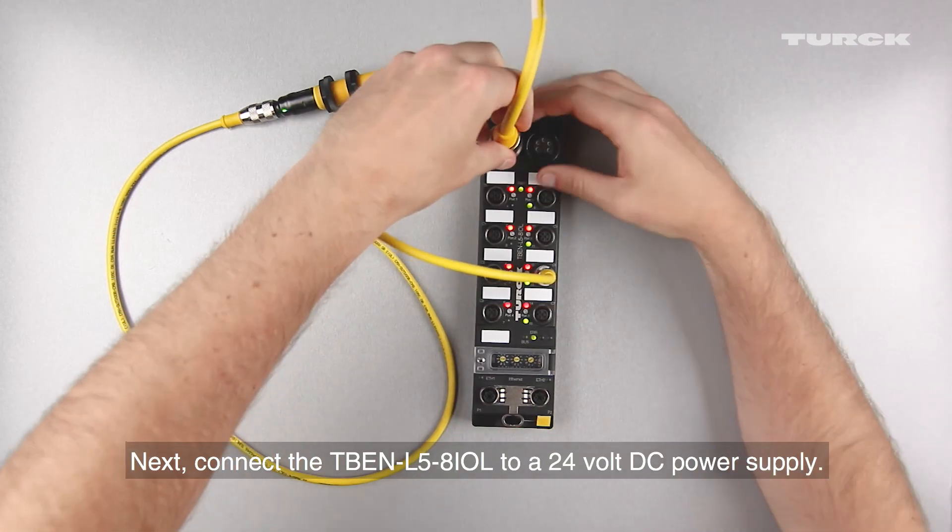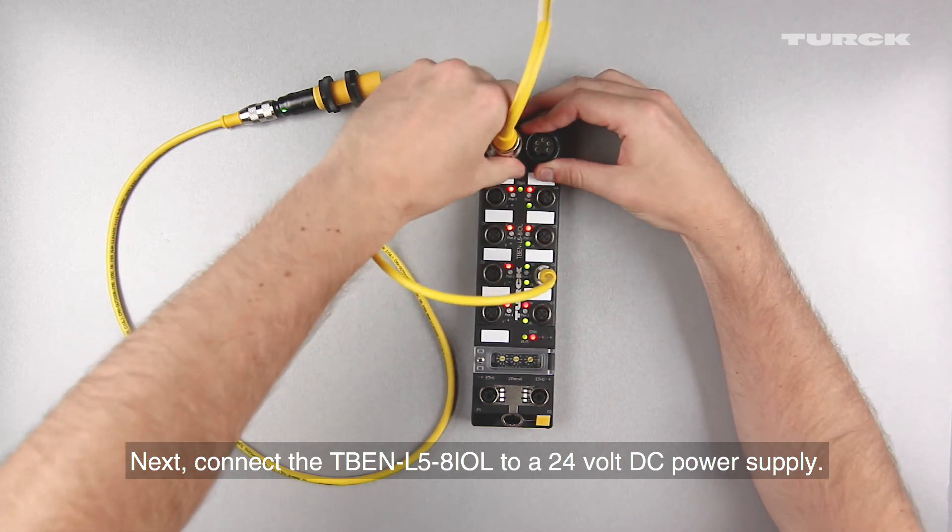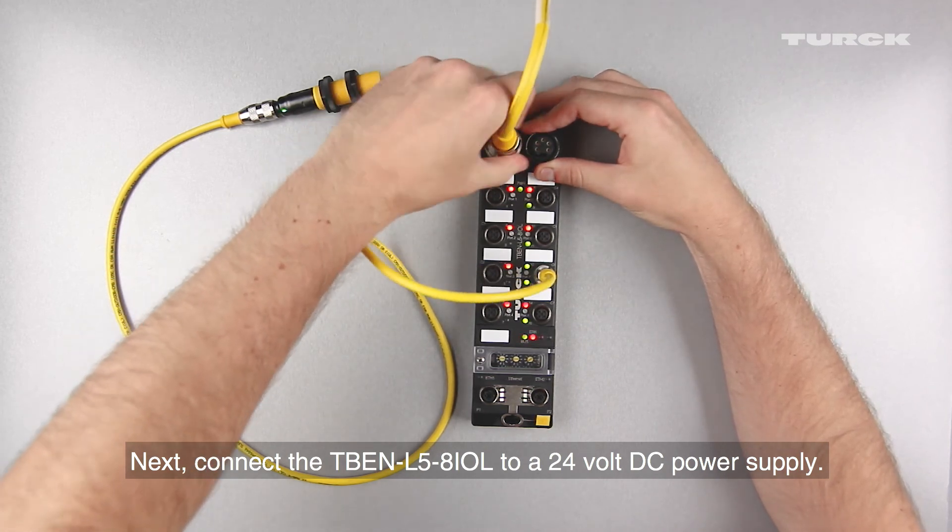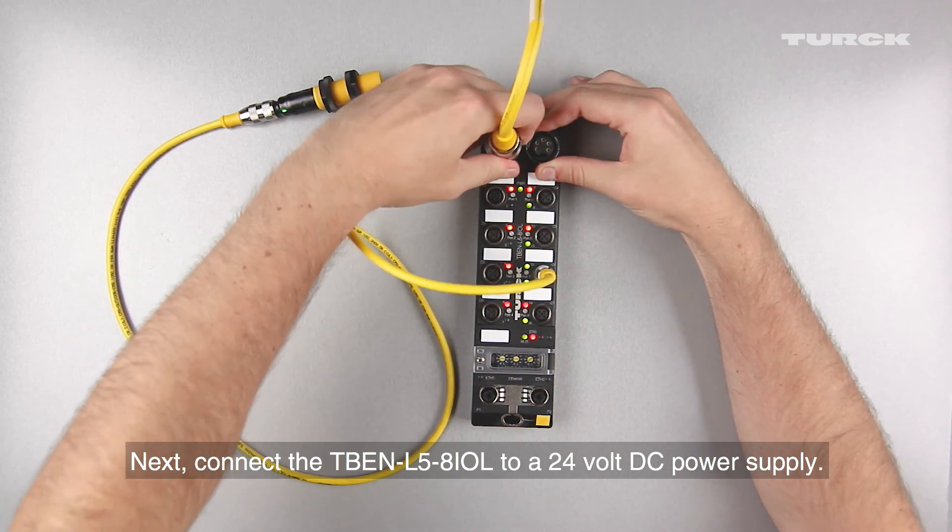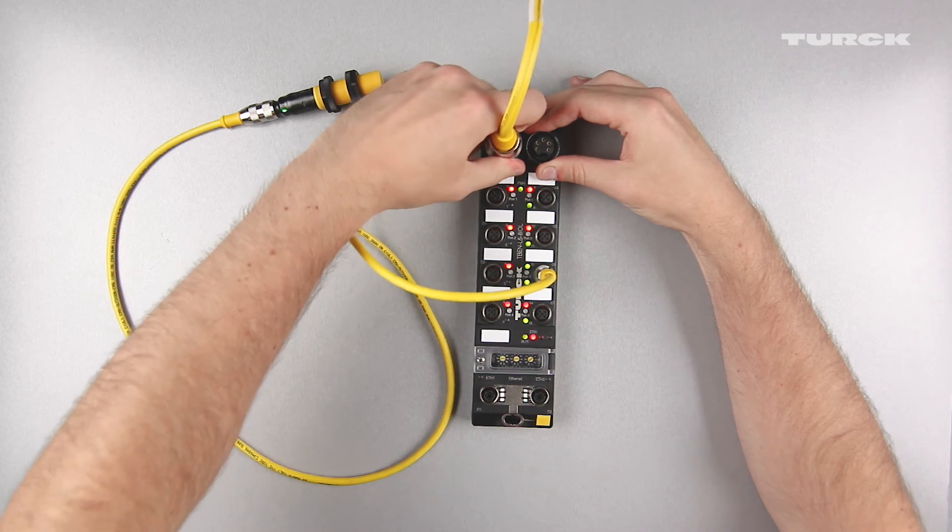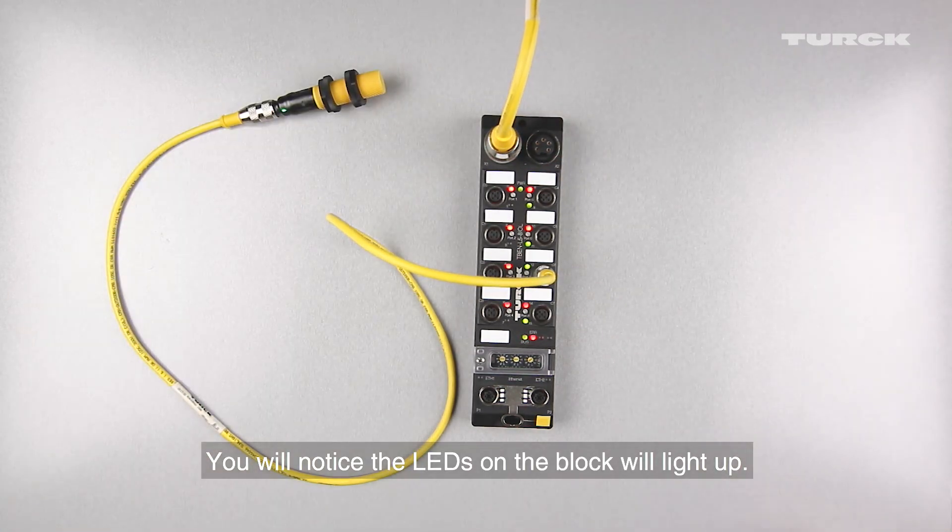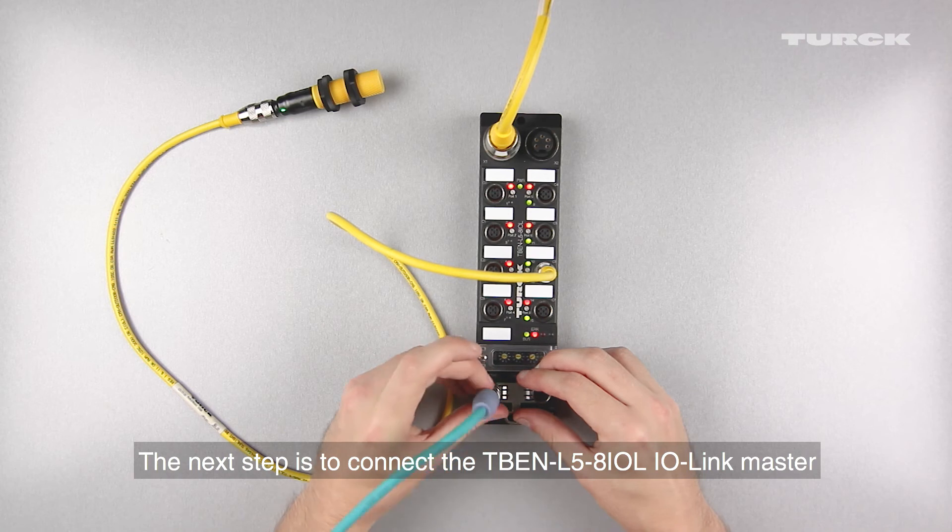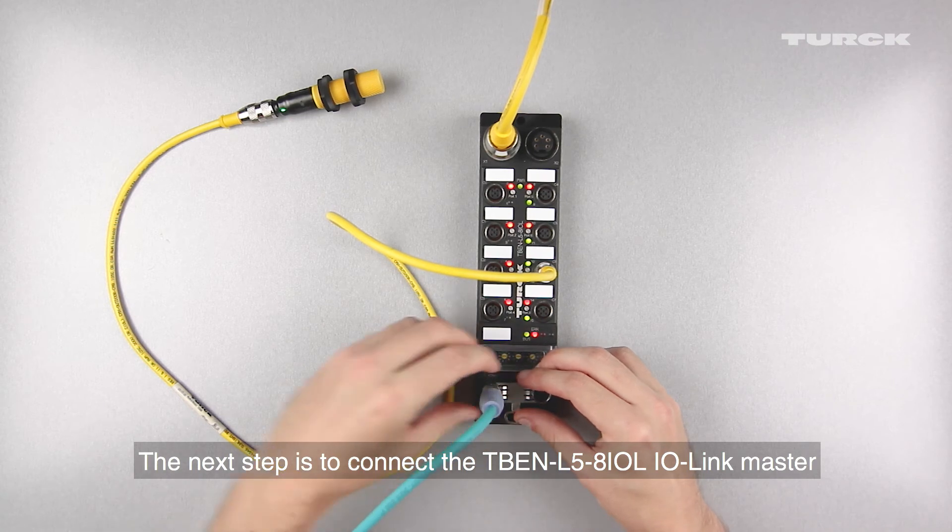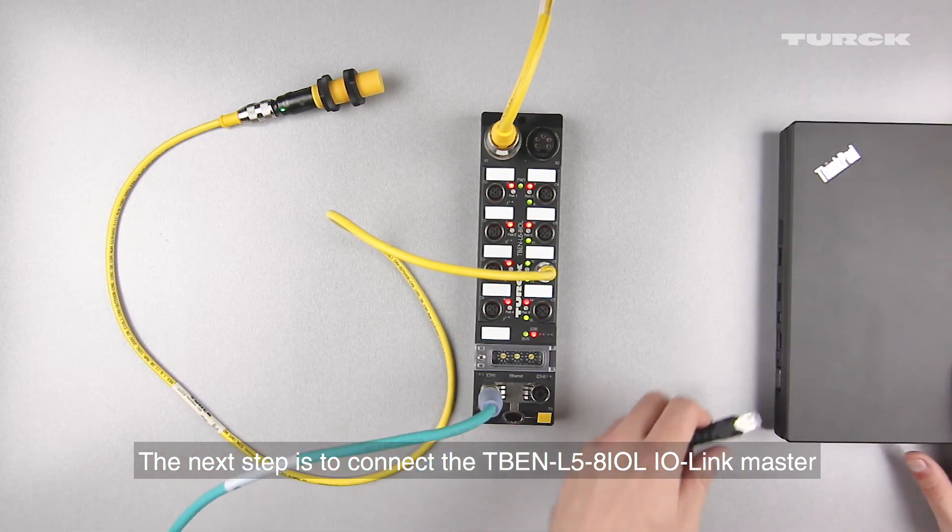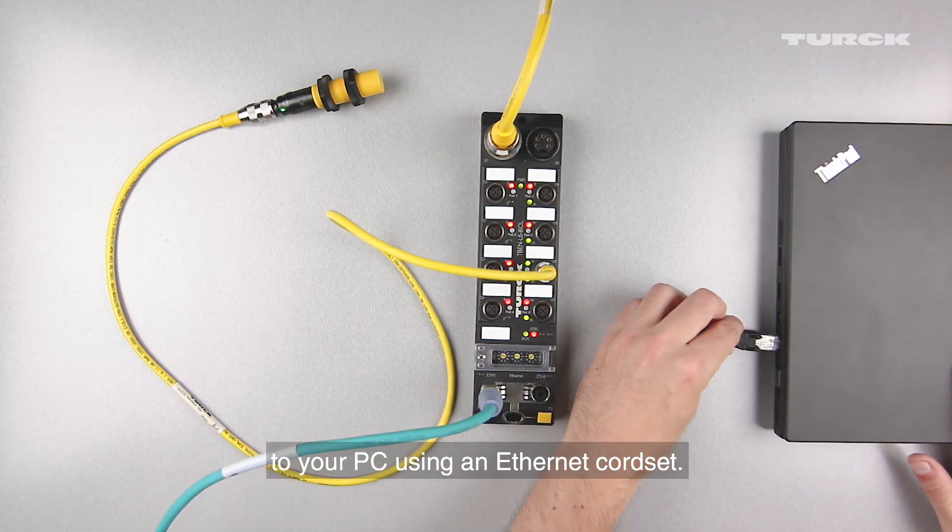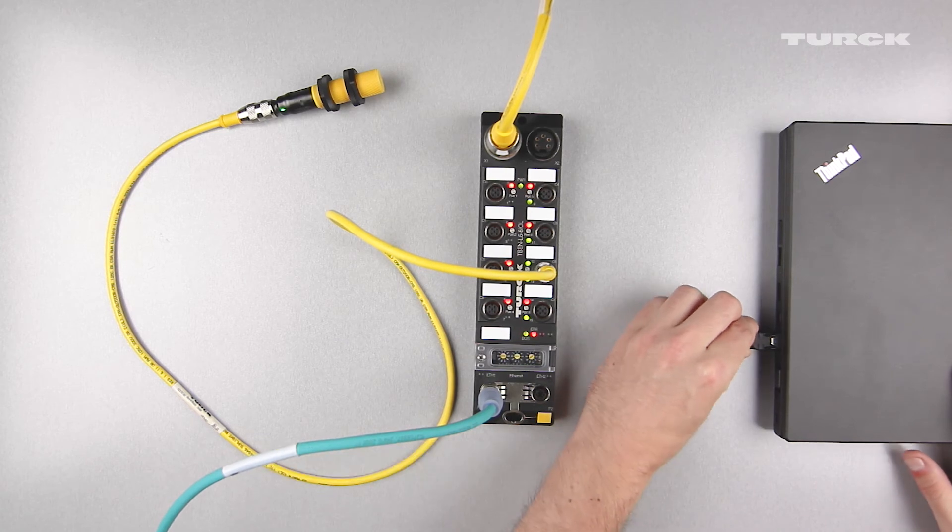Next, connect the TBEN L5-8IOL to a 24V DC power supply. You will notice the LEDs on the block will light up. The next step is to connect the TBEN L5-8IOL IO-Link master to your PC using an Ethernet cord set.